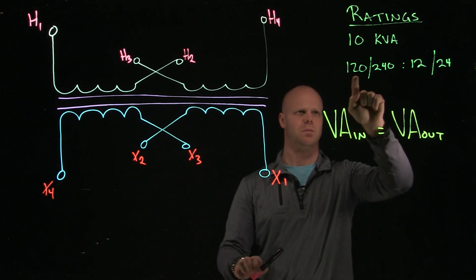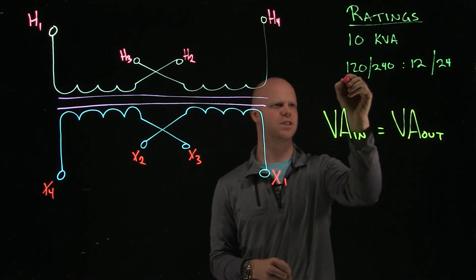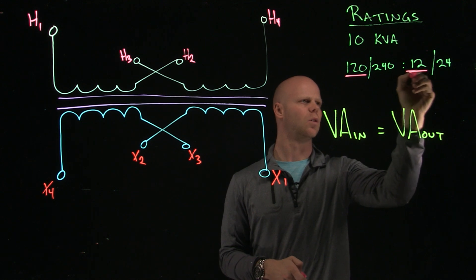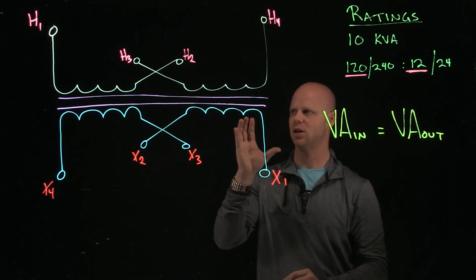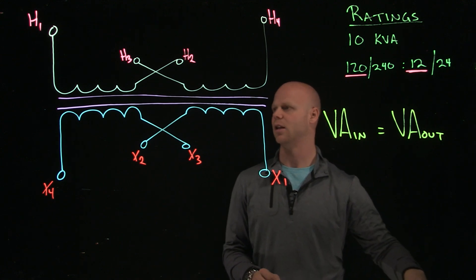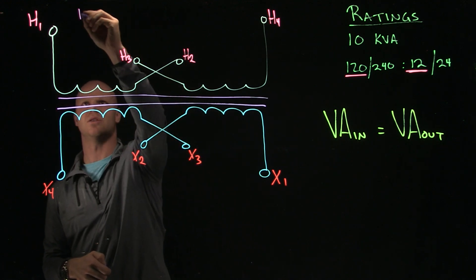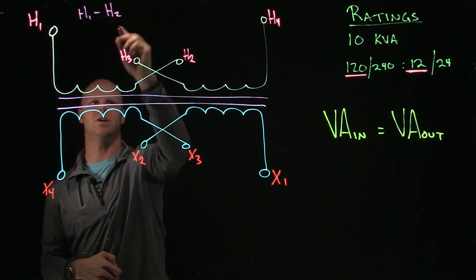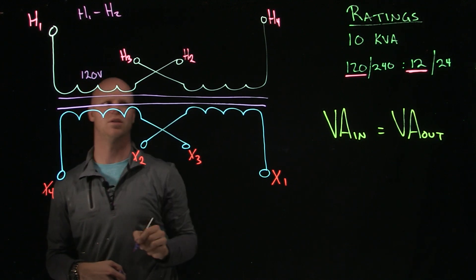So when I look at this multi-winding transformer with multiple voltages, this first value will always be the rating of one of the windings on one side. So if we follow that along, that means this H1, H2 winding, so H1 to H2, this winding itself will have a 120 volt rating.